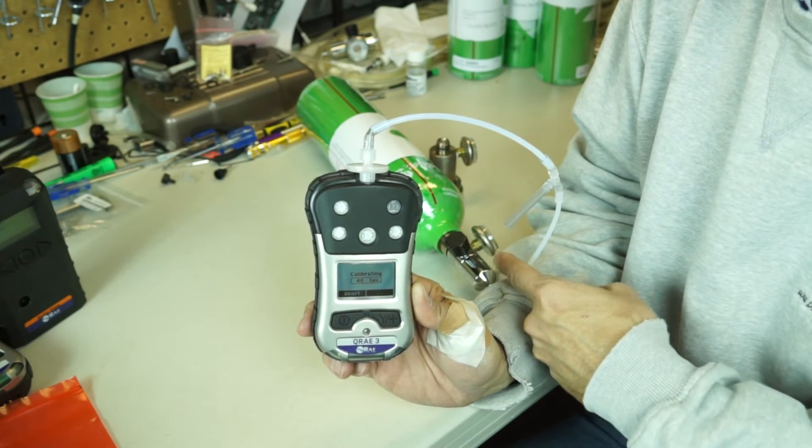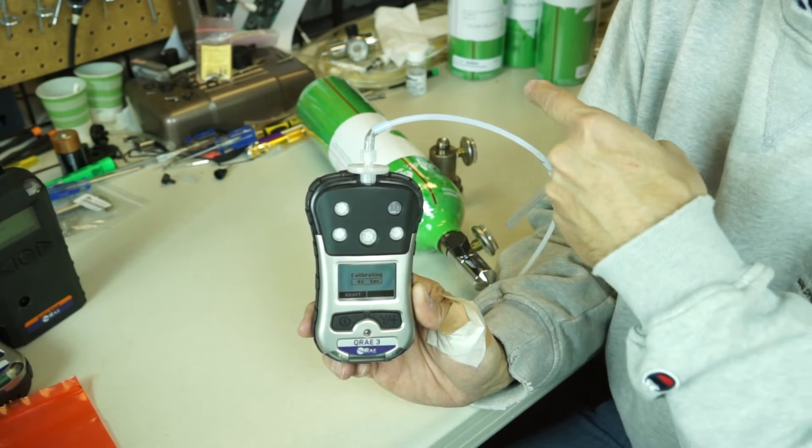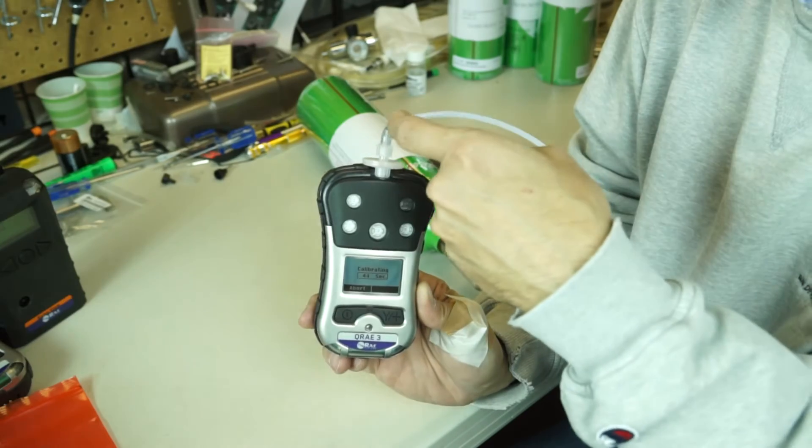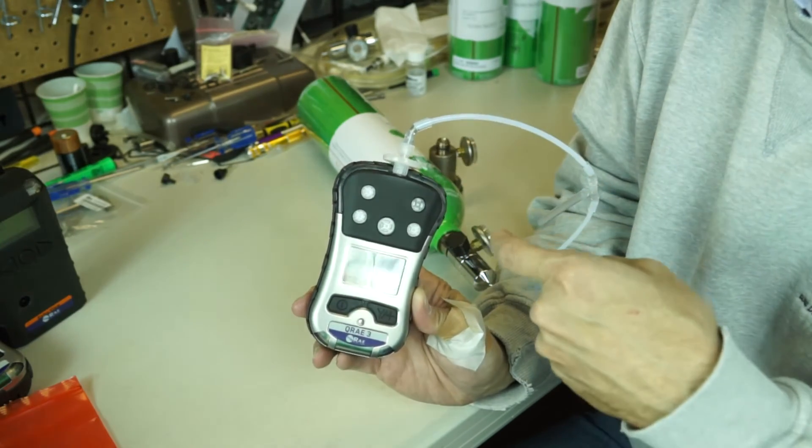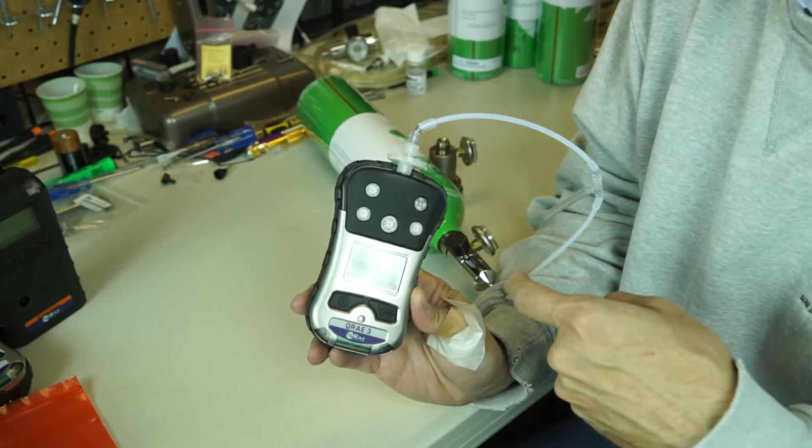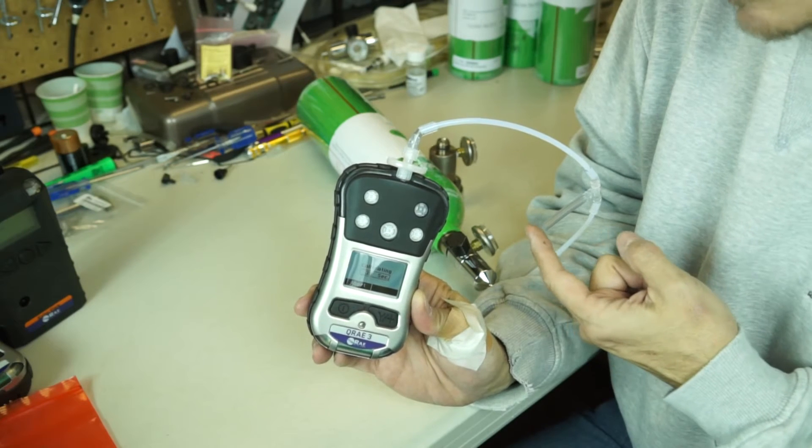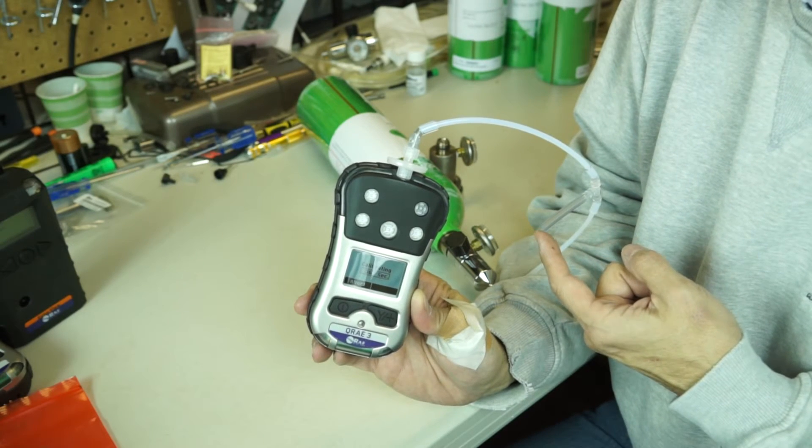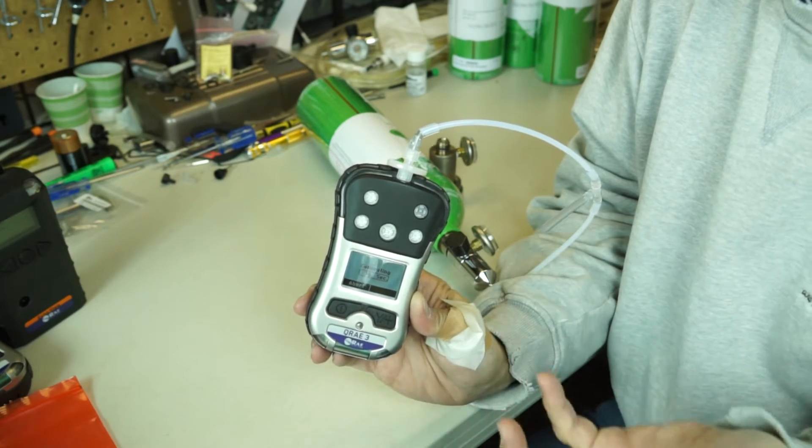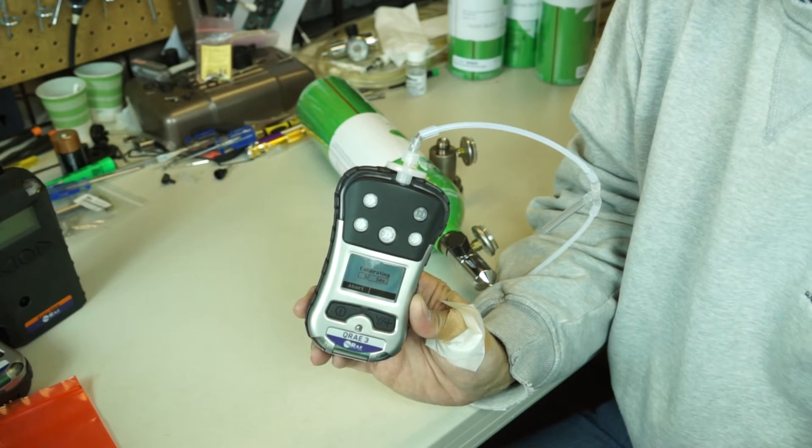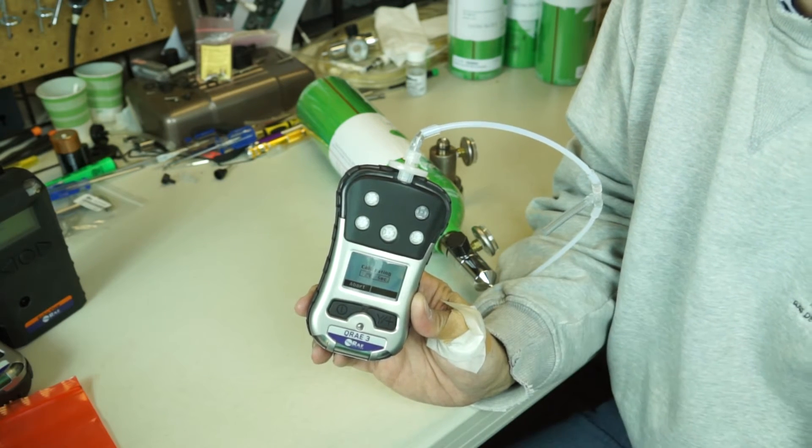So what's happening here, the gas is coming out. In this case a one liter per minute regulator. It's going right up into the instrument. And any excess is coming out the third leg. So what this means is the instrument is basically pulling at its own rate. The pump is pulling at its own rate. Any excess is coming out the third.